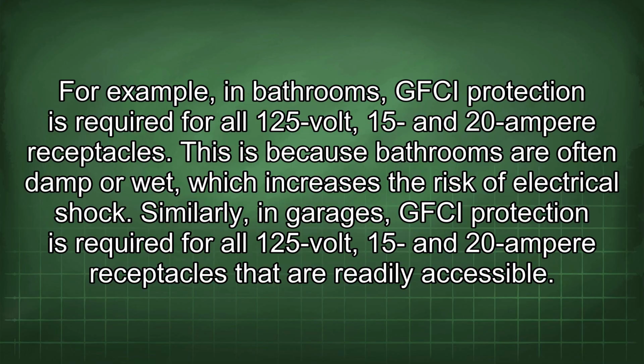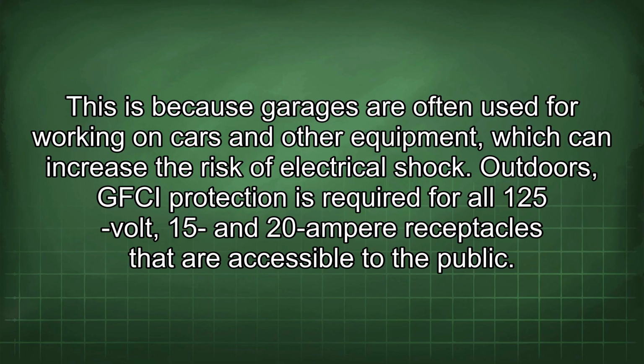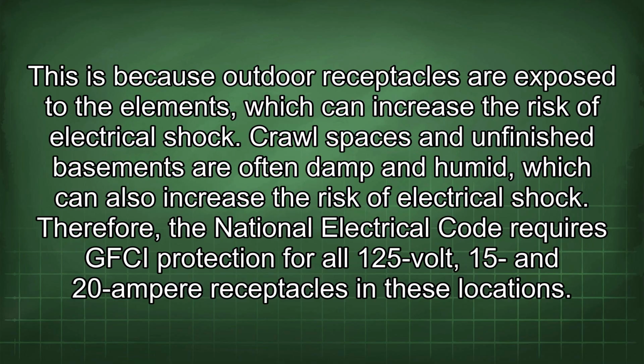Similarly, in garages, GFCI protection is required for all 125-volt, 15 and 20 ampere receptacles that are readily accessible. This is because garages are often used for working on cars and other equipment, which can increase the risk of electrical shock. Outdoors, GFCI protection is required for all 125-volt, 15 and 20 ampere receptacles that are accessible to the public. This is because outdoor receptacles are exposed to the elements, which can increase the risk of electrical shock. Crawl spaces and unfinished basements are often damp and humid, which can also increase the risk of electrical shock. Therefore, the National Electrical Code requires GFCI protection for all 125-volt, 15 and 20 ampere receptacles in these locations.